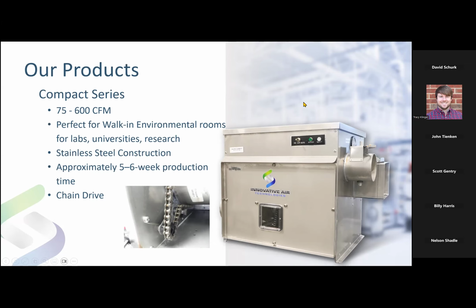Real quickly, a little bit about our products. We start with a small series that we call compact. It's compact because it's small. They're available in increments of 75, 150, 300, and 600 CFM. And everybody goes, gosh, how much moisture can you pull out of 600 CFM of air? Well, a lot. When you deeply dry it, I might be able to pull 25 pounds of moisture an hour out of a small 600 CFM airstream. That's a lot of moisture out of the air.